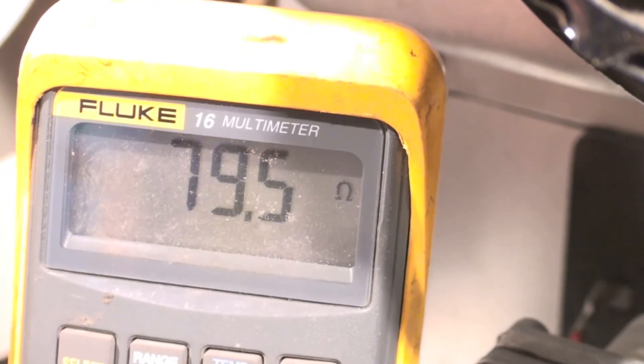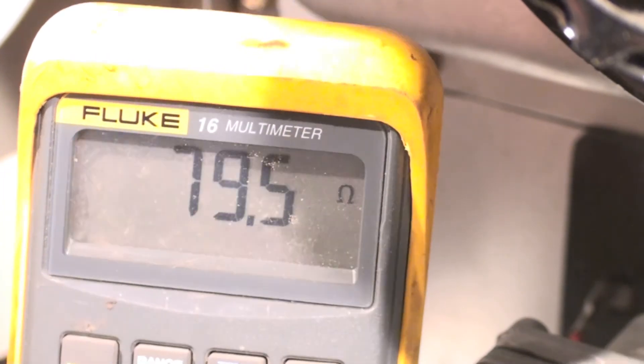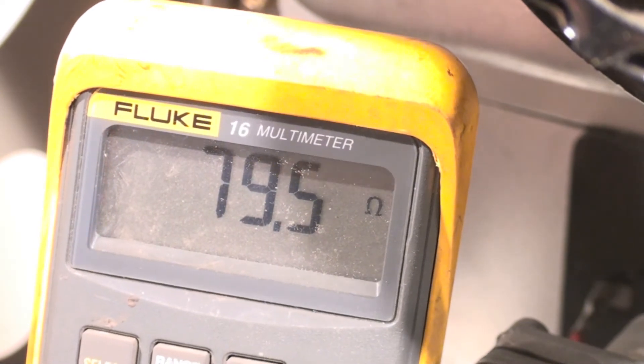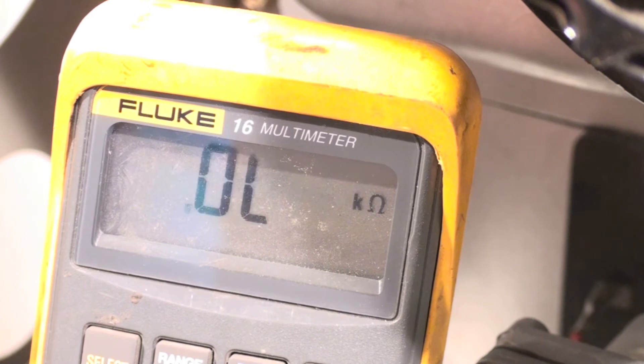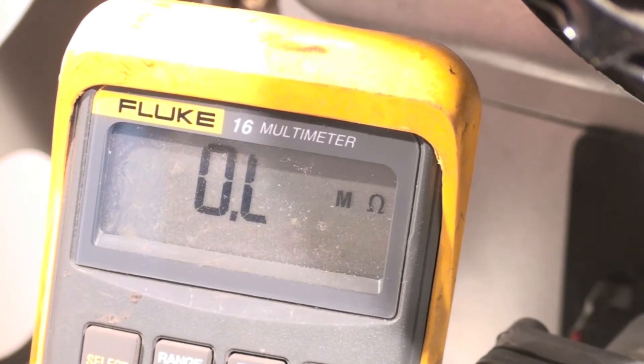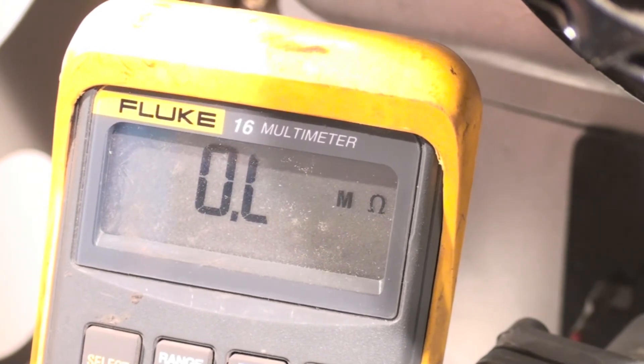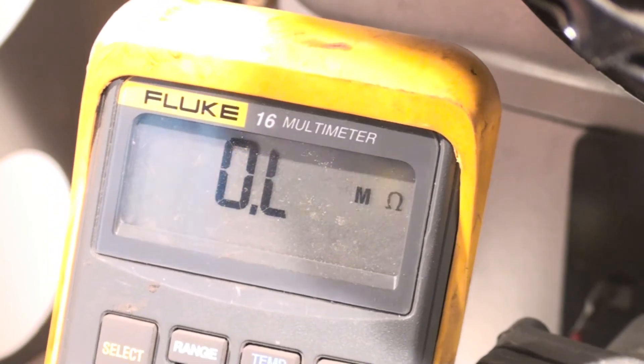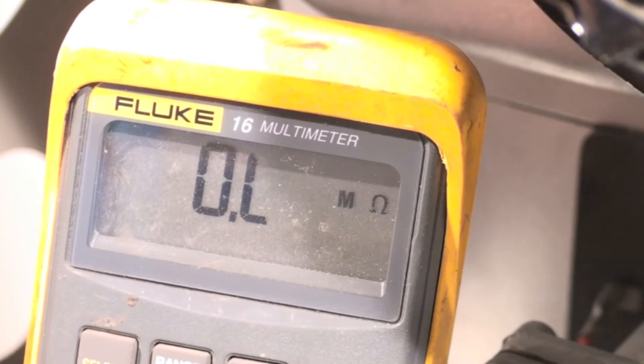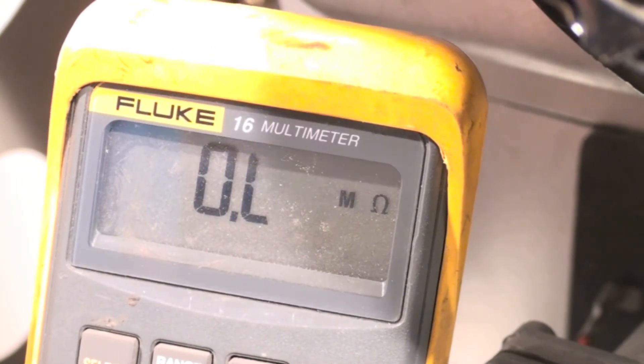If it was running 150 or higher, we would probably consider replacing. That's not a real accurate number, but it's a number we usually use on these things. Now if it read OL, that means the hot surface igniter has failed and the furnace is not going to light.